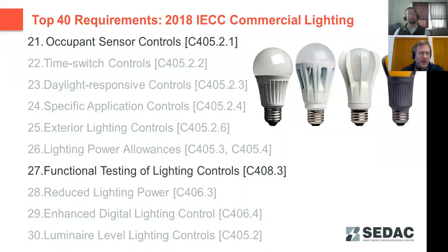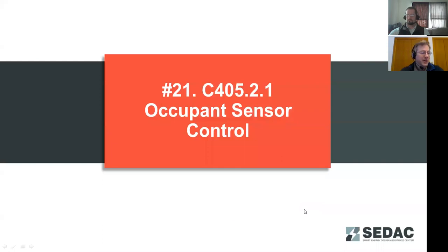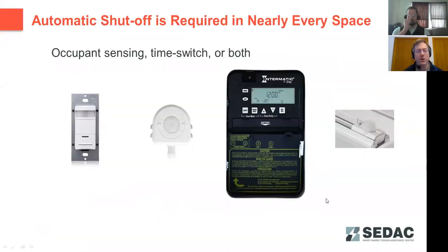Well, thank you, Sean. So here we're going to touch on two things, starting in the lighting area: occupant sensor controls, as well as some functional testing. Again, this commissioning comes back into play to make sure that systems are working as designed, so that the building owners are getting the value that they've paid for as part of construction. Starting with our occupant sensor controls, I will try to be cognizant of using occupant sensor controls rather than occupancy sensing controls, because both occupancy sensing and vacancy sensing are occupant sensing methodologies.